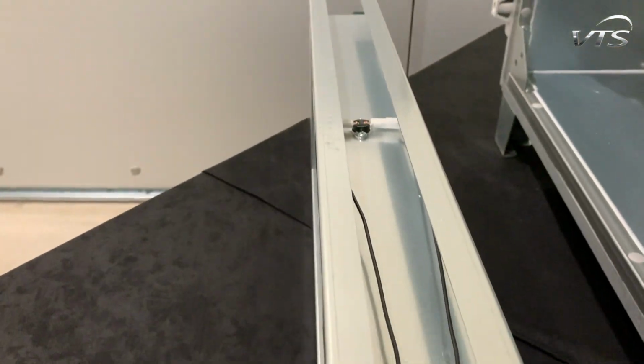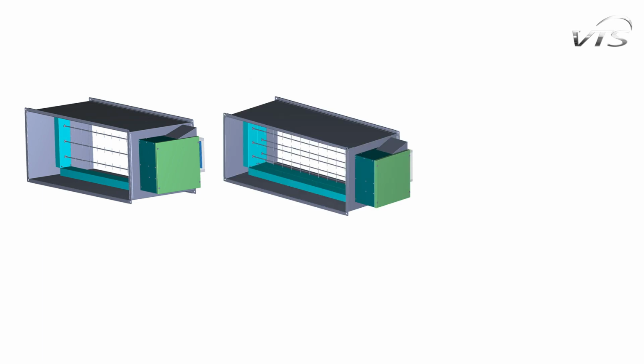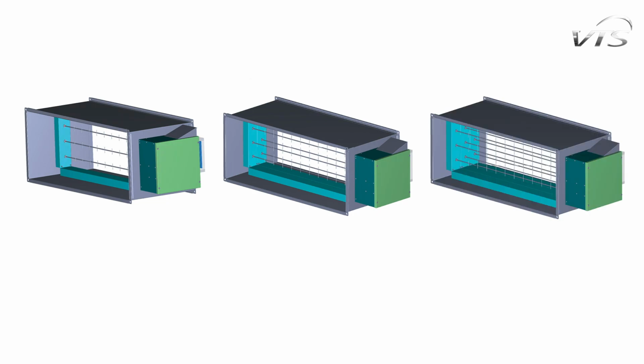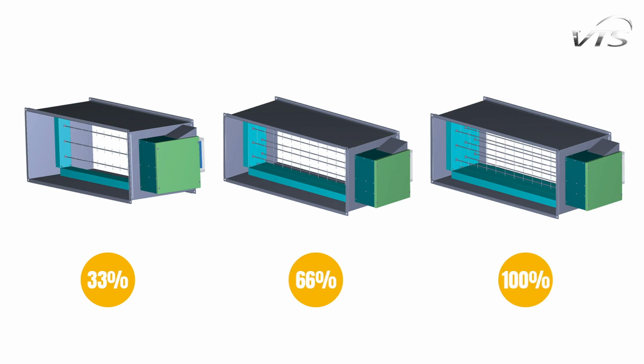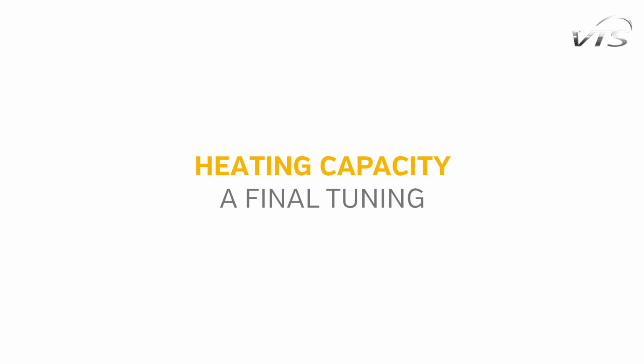We call them slices. By increasing the number of heating slices, we can easily increase the heating capacity by relatively small intervals. Thanks to such an approach, each heater can be factory sized for 33, 66 or 100% of its maximum output power. Heating capacity, a final tuning.